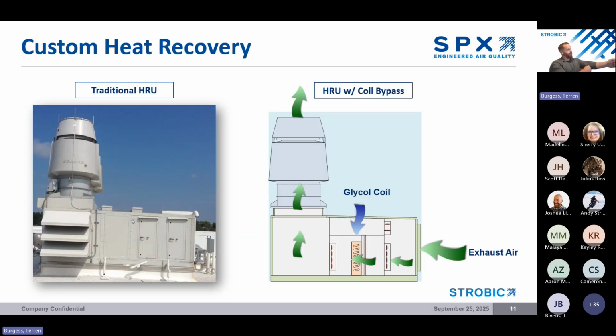So heat recovery, I'd mentioned that a few slides back. And when we talk about laboratory design, one of the biggest challenges we're going to face is energy use, right? And I've already covered that labs can be some of the most energy intensive buildings out there. It's driven heavily by the exhaust system. So the issue lies in the exhaust air is conditioned air. It's already been heated, cooled, right, to make that space comfortable. And we're going to throw it right outside. So without any recovery, you're dumping energy and money right out the stack.